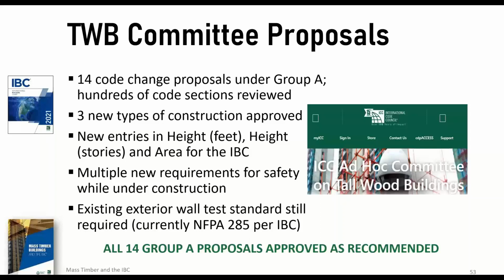There are a slew of new requirements for fire safety during construction, and they determined that an existing exterior wall test standard is still applicable, even though that NFPA 285 testing standard is one that's used for non-combustible walls. They figured that the stringency of that test would be well suited to be applied to the combustible form of construction, albeit with fire resistance and non-combustible gypsum and the inherent fire resistance of mass timber. It'd still be prudent to make sure those assemblies are tested in accordance with NFPA 285.